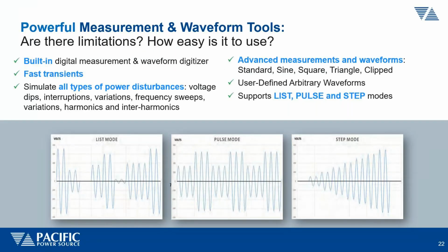Finally, we're looking at flexibility in terms of functionality. Grids usually use a sine wave for voltage and current, but in the real world you want to simulate real conditions, which aren't always sinusoidal. So having programmable and arbitrary waveforms is important—you want to create your own arbitrary waveforms or select from a library of preset harmonic waveforms. You also want the ability to program transients, and grid simulators usually offer list mode, pulse mode, or step mode, sometimes all three.